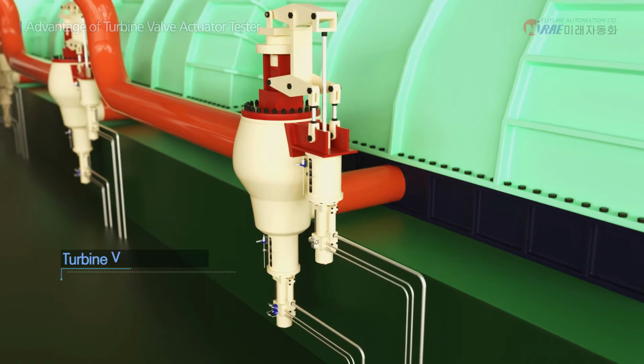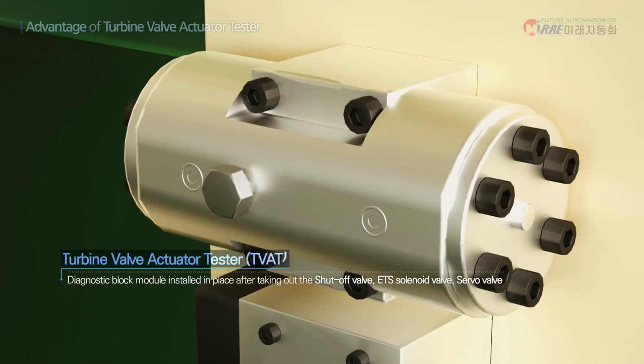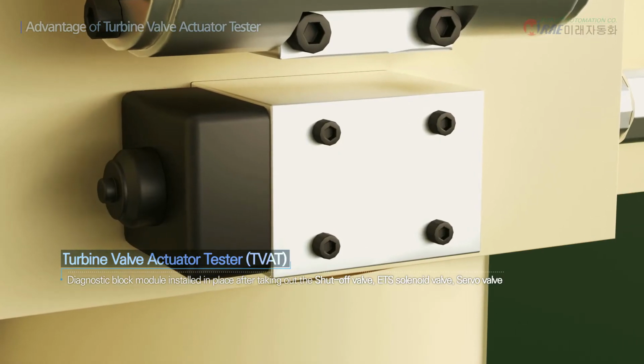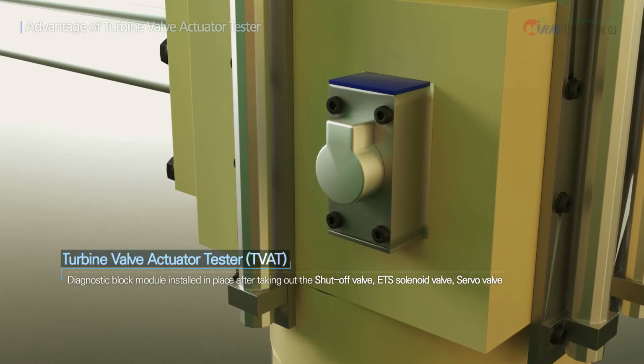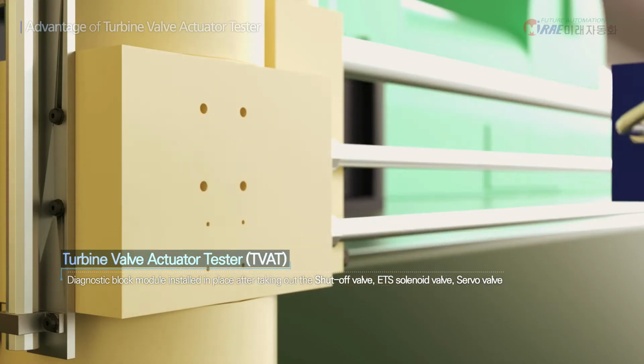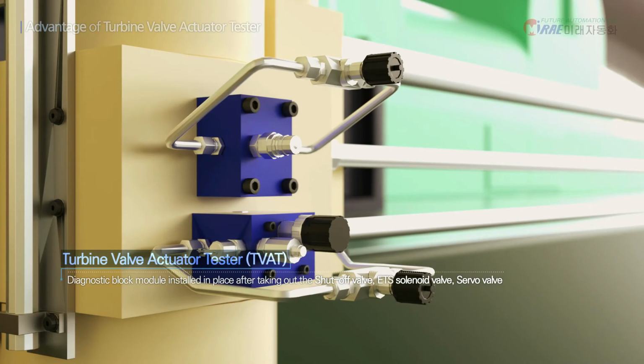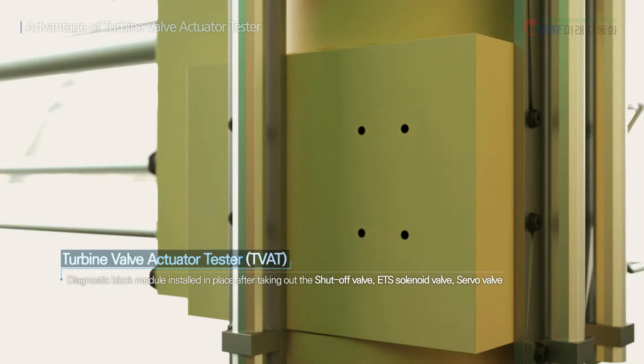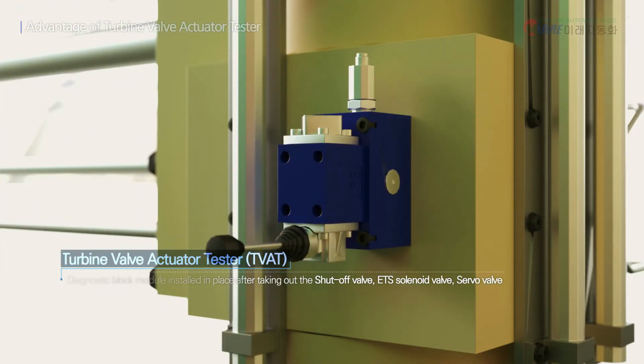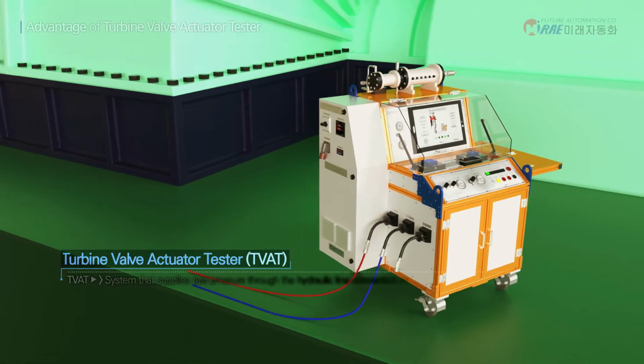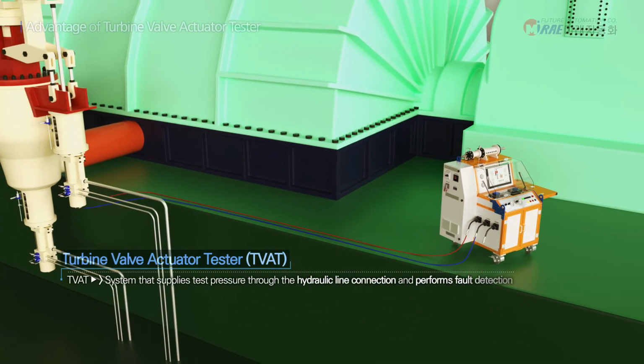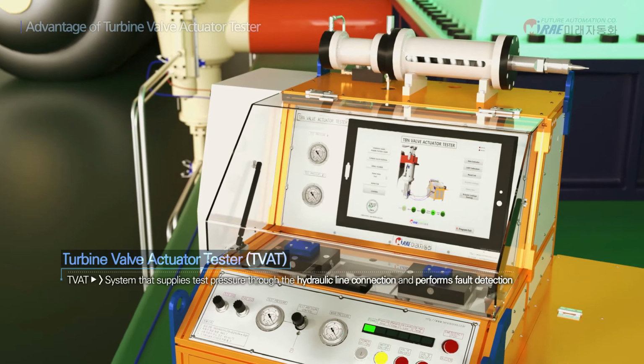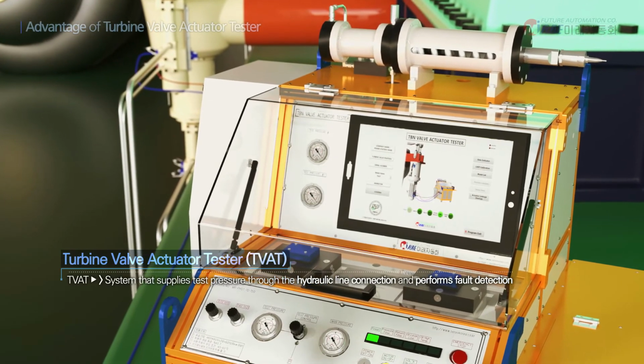The diagnostic block module is installed in place after taking out the shutoff valve, ETS solenoid valve, and servo valve attached to the actuator. The Turbine Valve Actuator Tester supplies test pressure through the hydraulic line connection and performs fault detection. Diagnostic result data can be saved and printed out as a report.